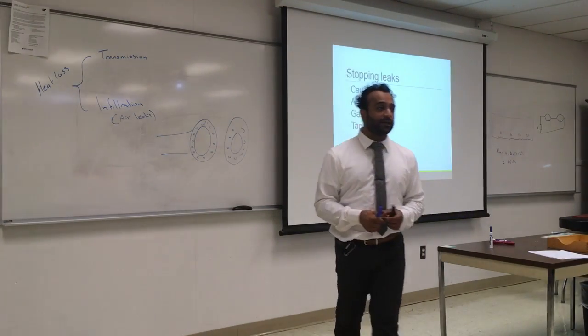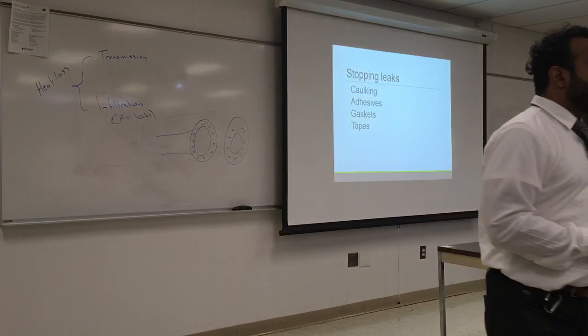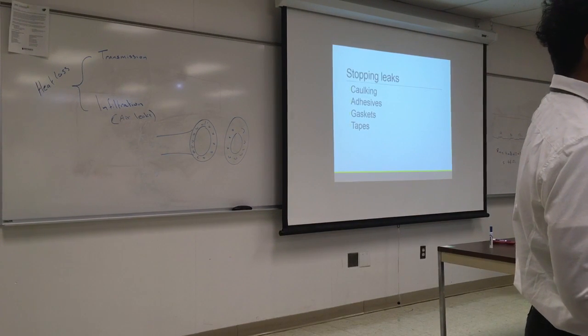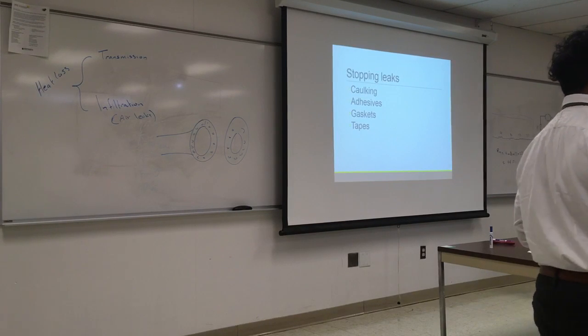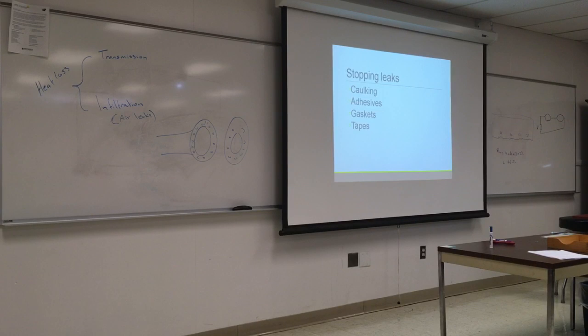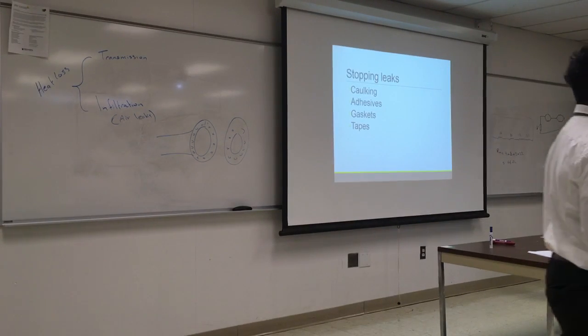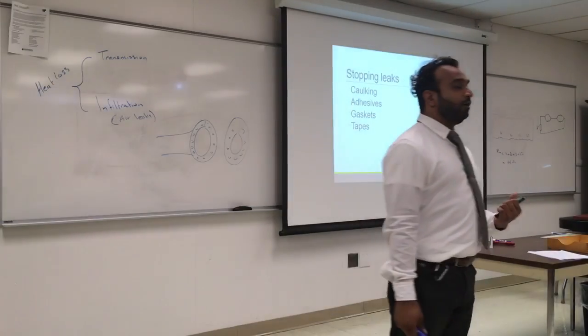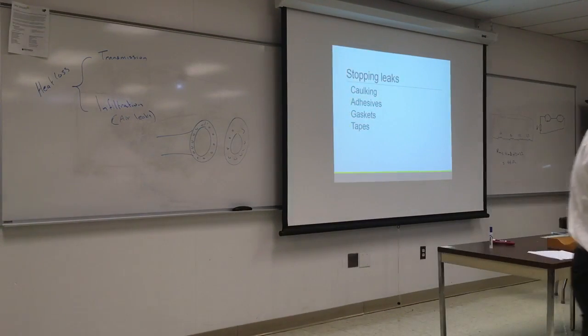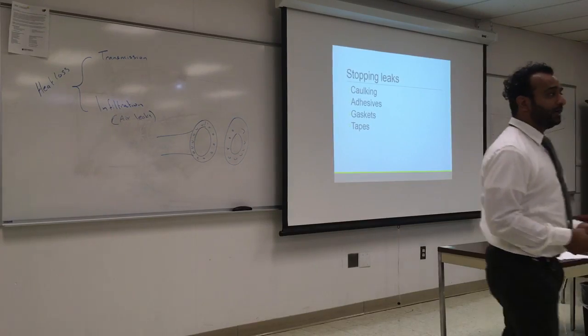Tapes. Plenty of tapes. Tapes could be a problem if it's not heat resistant because if you run a furnace and you have hot air duct and air is going through it, the air can be as high as 180 degrees Fahrenheit. So if that tape has some glue that is combustible, it might be a problem to have that in there. And also something you want to be aware of is when you have a lot of ductwork in the house and it has hot air, make sure there's no combustible material around it. Some kind of combustible insulation, some paper insulation. And over time it will dry out and it might catch a fire.